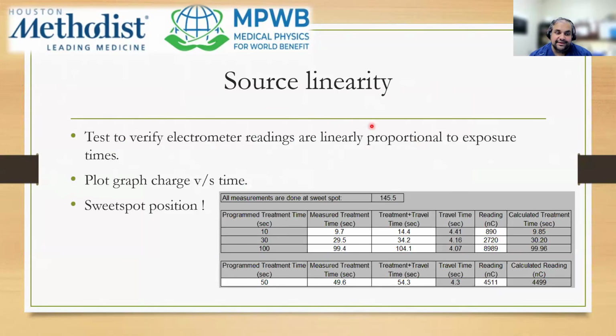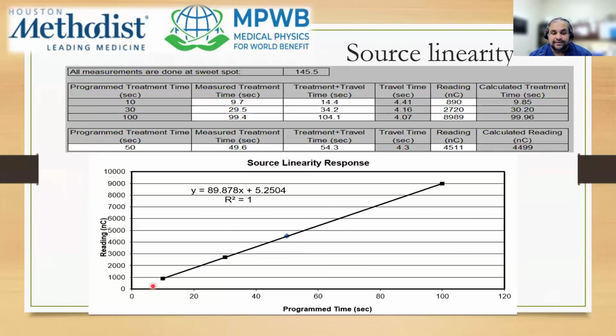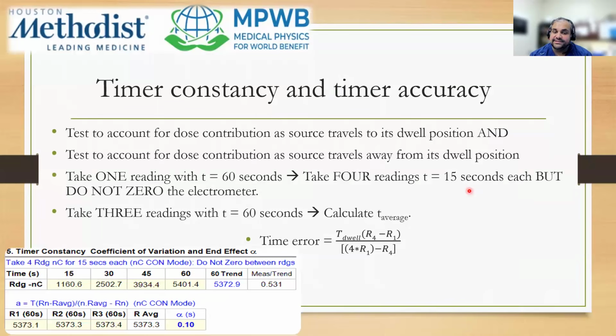Next is the source linearity test. It basically tests to verify the electrometer readings are linearly proportional to your exposure time. Like I mentioned, it's done at the sweet spot position, and you usually get a linear response. You have your timer constancy check. This takes into account your transit dose, which is the dose delivered to a dwell position while the source travels to the position and travels back from the position. Your tolerance level should be less than 1 second.